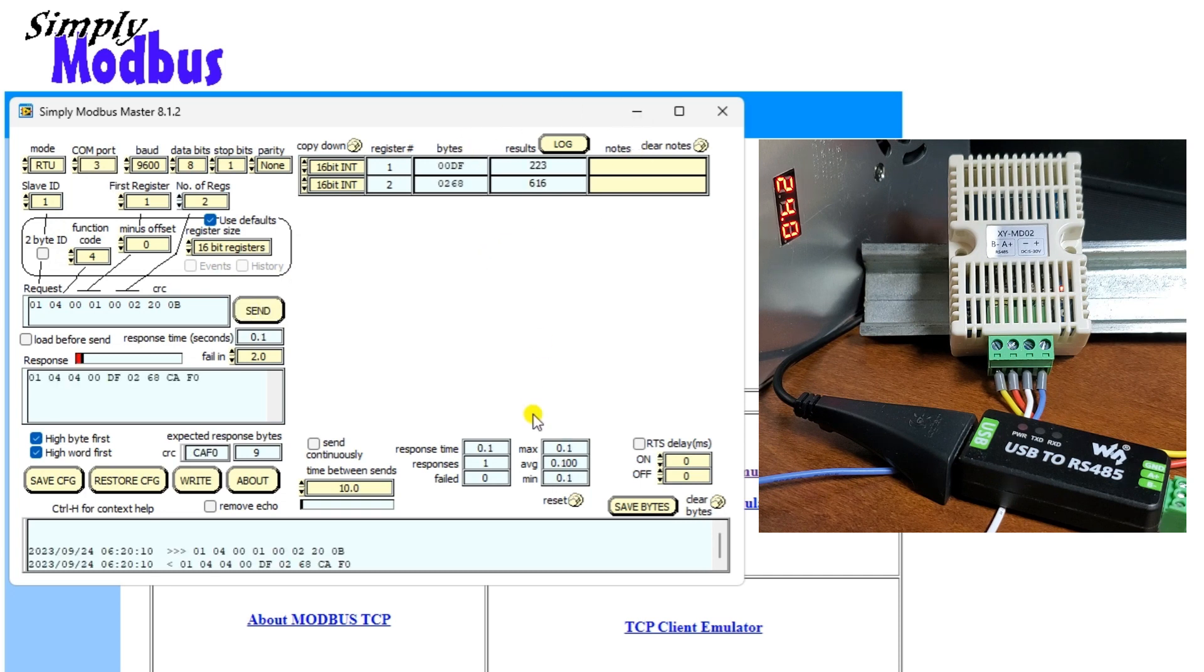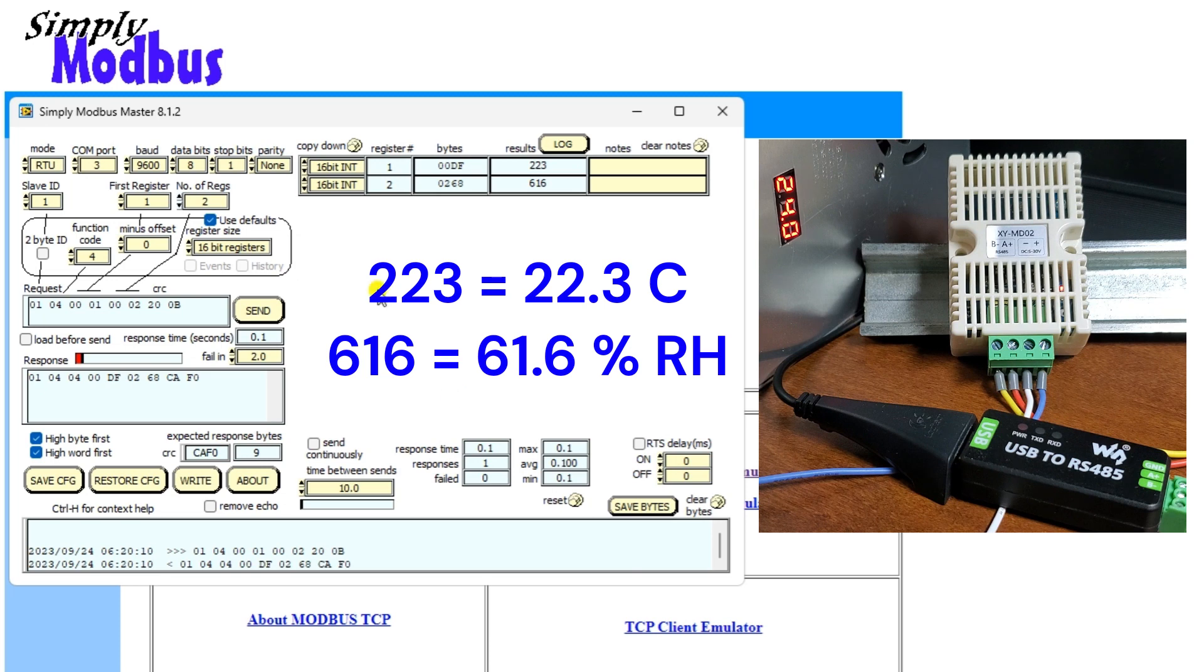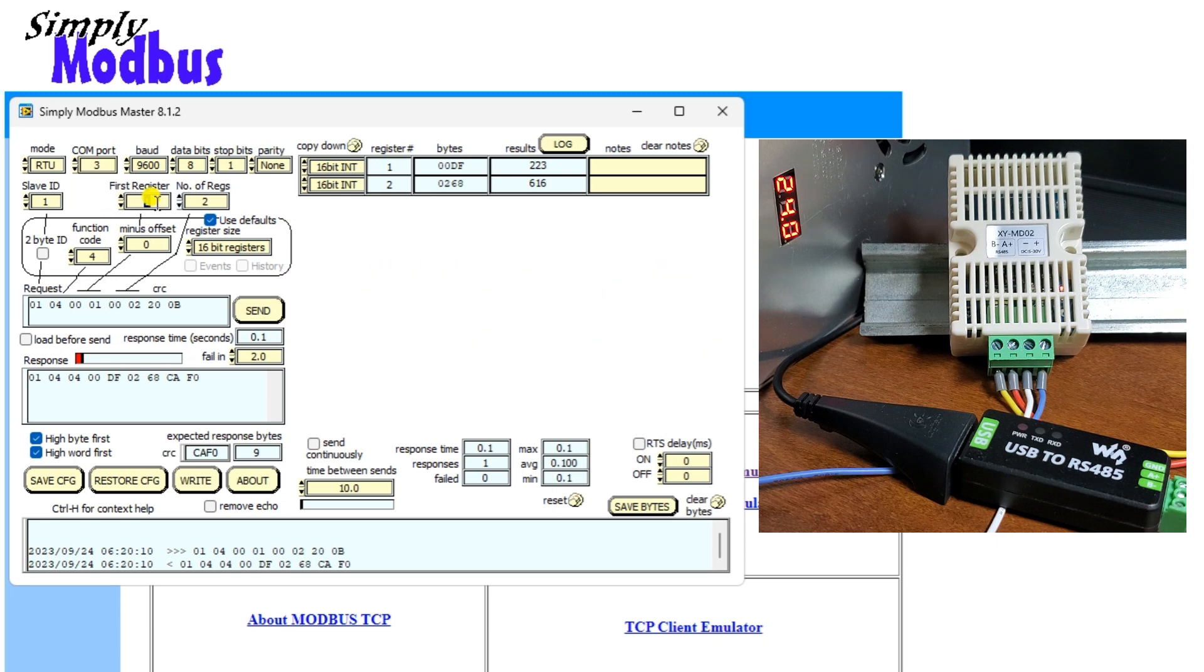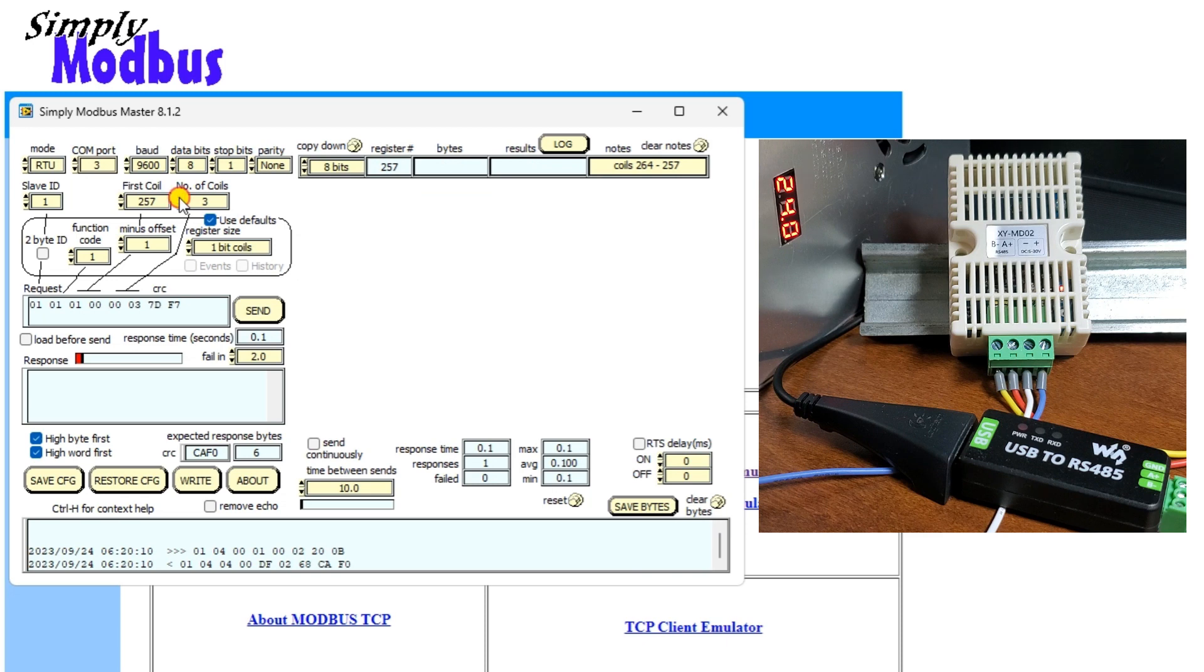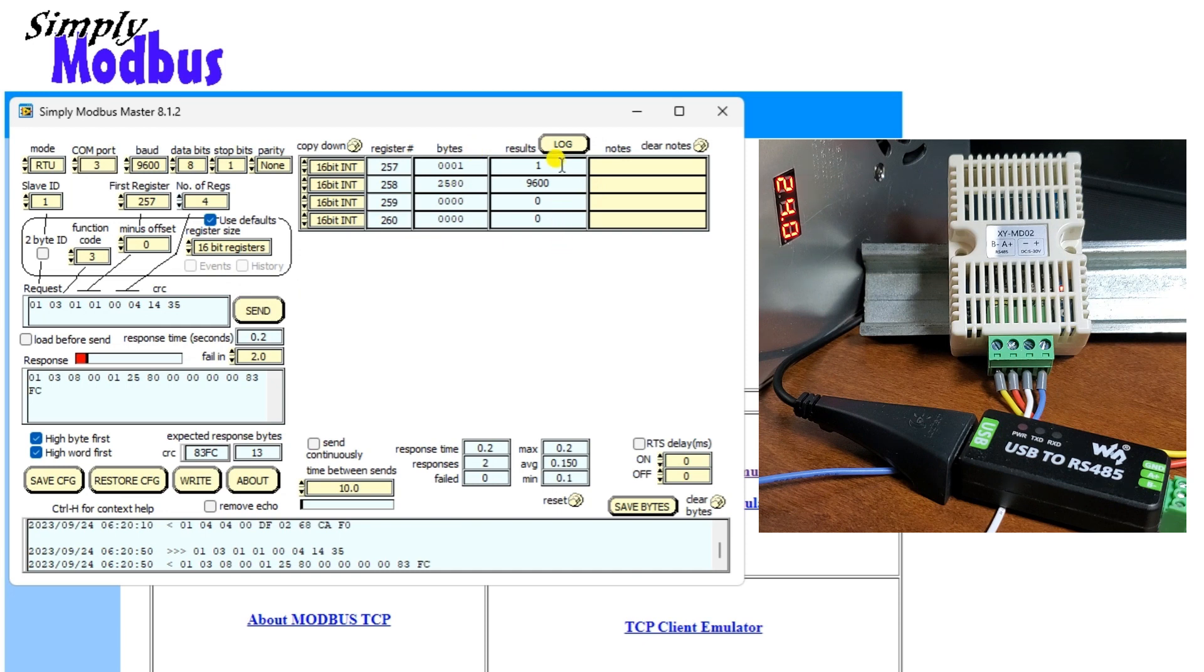Note that one decimal place is understood. 16-bit registers will be read. Changing the first register to 257, which is 101 hex, and setting the function code to 3 and reading four registers will show you the parameters for the XY-MD02 sensor. This data represents the address number, baud rate, temperature offset, and humidity offset.